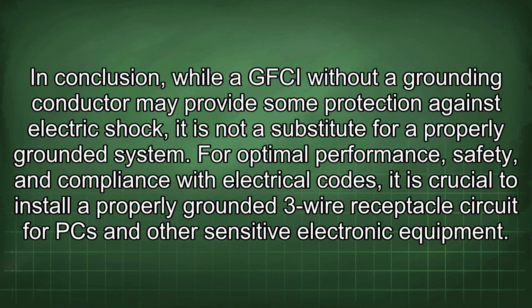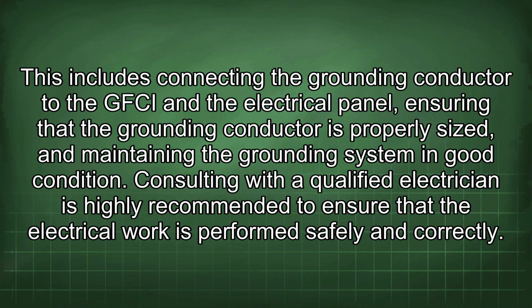In conclusion, while a GFCI without a grounding conductor may provide some protection against electric shock, it is not a substitute for a properly grounded system. For optimal performance, safety, and compliance with electrical codes, it is crucial to install a properly grounded 3-wire receptacle circuit for PC and other sensitive electronic equipment. This includes connecting the grounding conductor to the GFCI and the electrical panel, ensuring that the grounding conductor is properly sized, and maintaining the grounding system in good condition. Consulting with a qualified electrician is highly recommended to ensure that the electrical work is performed safely and correctly.